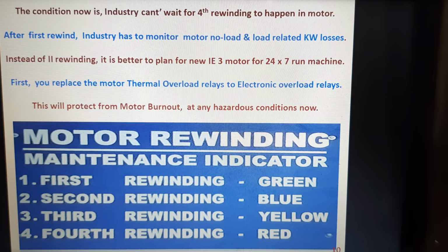The condition prevailing in the industry is that the industry cannot wait for the fourth rewinding to happen in your motor. You can see the diagram below. It is taken from the notice board of a given industry where we have done an energy audit. We noticed this and also told the industry to immediately replace the motor after the first rewinding. After the first rewinding, the industry has to monitor the motor's no load and load related kilowatt losses, and instead of going for a second or third rewinding, it is better to replace it with a new IE3 or IE4 motor for their 24/7 running machine, because this caters to a flat and excellent efficiency over a wide range of loading.